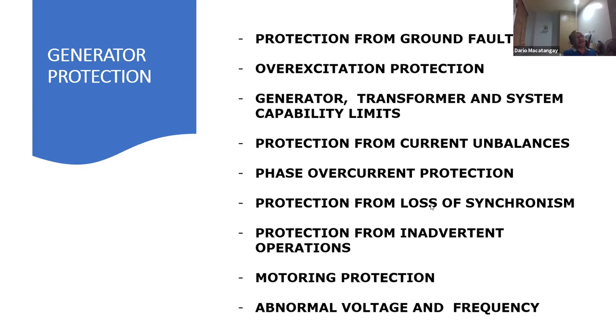Because if you lose synchronism, that indicates you're losing step. It's going to be an out of step operation. In other words, the magnetic field of the rotor is not synchronized anymore with the power system itself. You lose synchronism. When you get out of step, you can easily damage the generator because of the pulsating current. It's going to be an unstable operation.